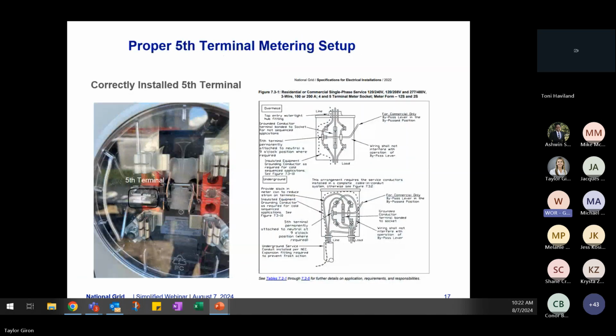And then here I have figure 7.2-1, which shows a typical 100 amp and 200 amp residential 4 and 5 terminal meter socket, for single phase 120/240 volt at the top, and 208 volt at the bottom with the fifth terminal, with a picture of a properly installed fifth terminal on the left to depict how that should look when installations occur in the field, to prevent any delays. Next slide, please.